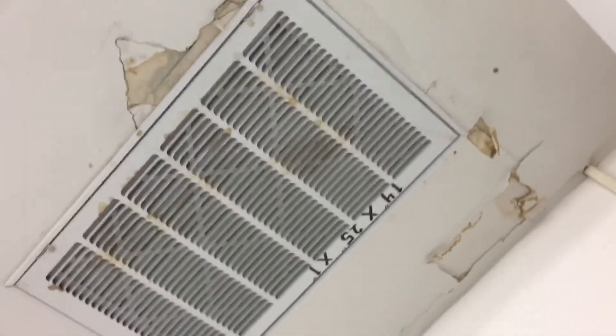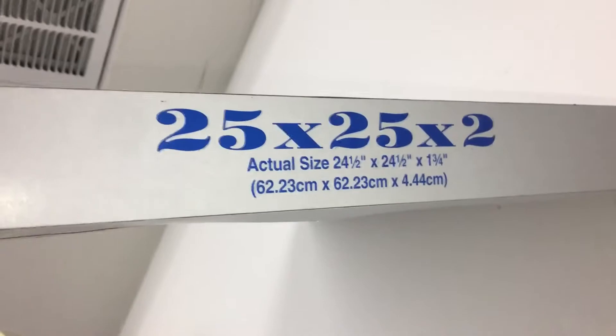What do they have in the single room? 14 by 25. So it's like getting an athlete and putting a plastic bag over his head, sticking a straw in his mouth, and saying compete against the other competitors. Since this is one of the rooms on a zone system, I'm going to put in 25 by 25 by 2.